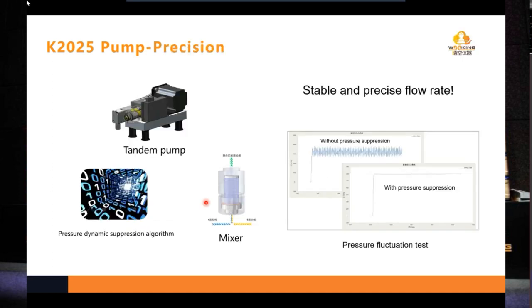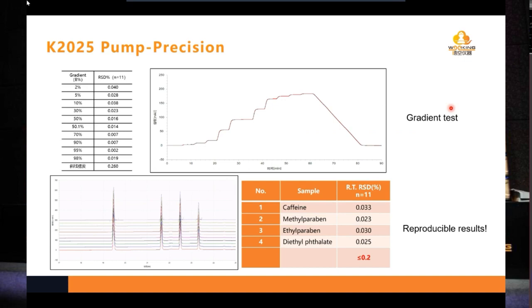And for better precision, we are using a tandem pump, or called a serial pump design. It is a very classical design, a proven structure for better performance. We use a pressure dynamic suppression system to reduce the pressure pulsation. And we have a well-designed mixer for the solvent mixing to ensure a stable and precise flow rate. We did some tests for the precision performance. The picture on the top is called a gradient test. It seems like one graph in here, but actually it is an overlaid result of 11 experiments.